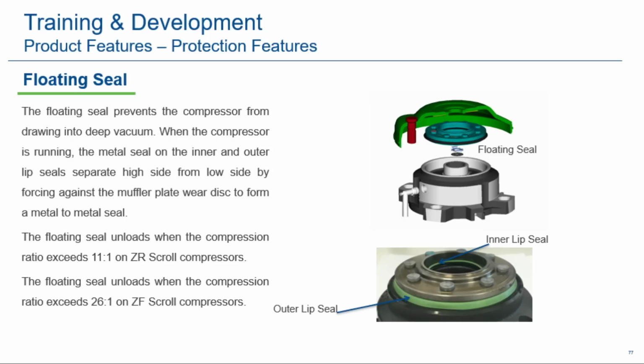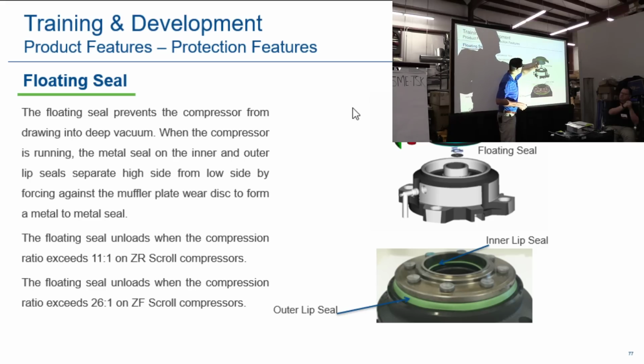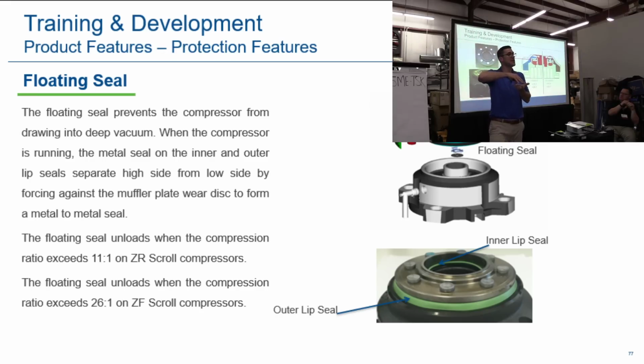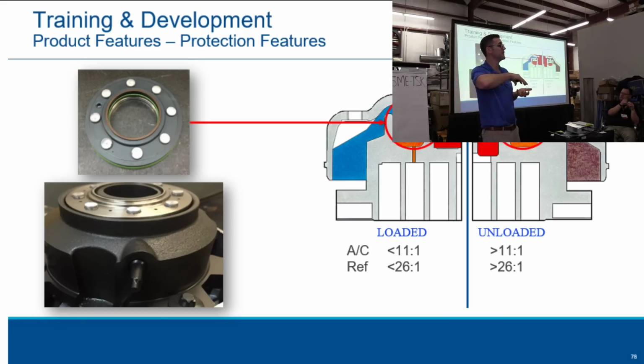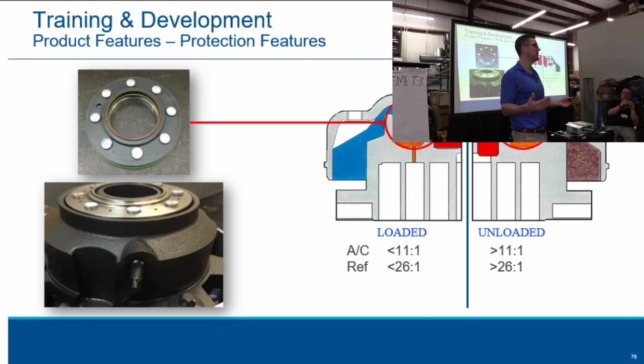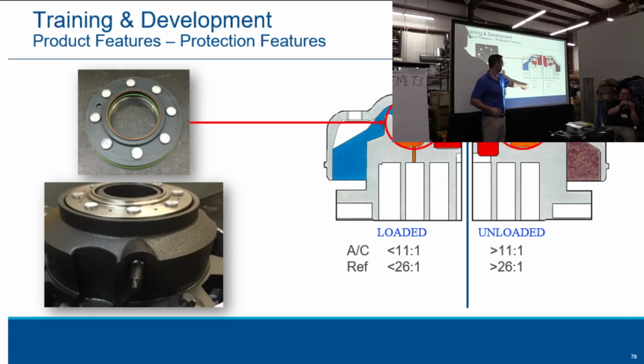But on this floating seal design, right along the top here is this little metal piece. This is called the muffler. When the scroll compressor starts unloaded, this pushes up against the muffler plate, which pushes down the fixed scroll. Inside the scroll set there's a little hole, and that intermediate stage pressure pushes up on the bottom to mate those scroll sets as it pumps. So when you start to get a high compression ratio, what is compression ratio? Can anyone tell me? Your absolute suction to absolute head. Yeah, exactly, so you divide them. If you're below 11 to 1, the compressor's going to pump fine. If you get over 11 to 1, it's going to unload.